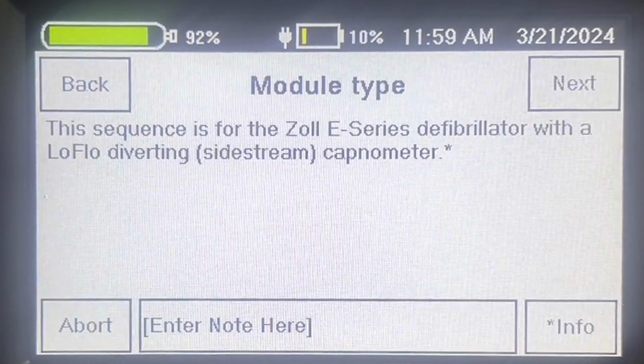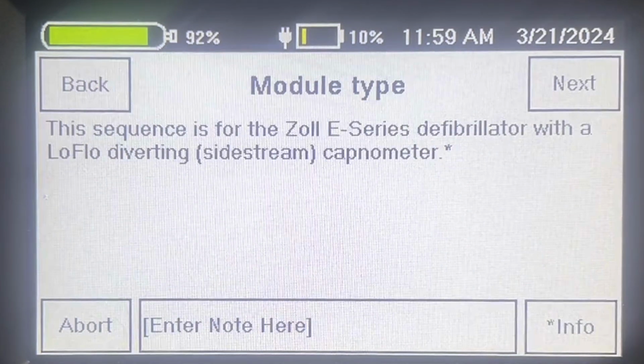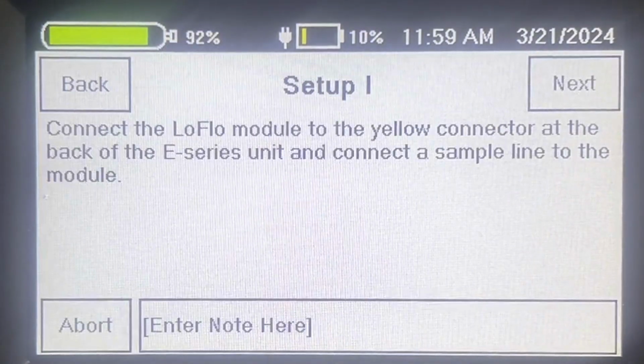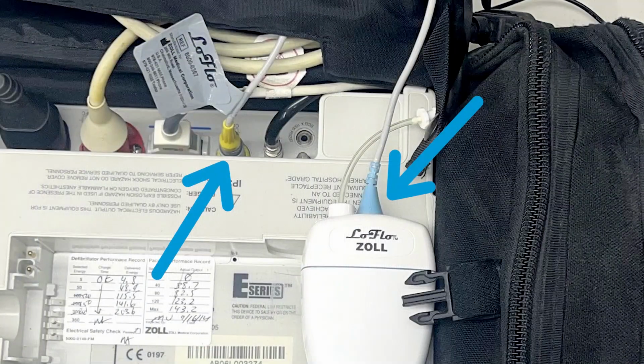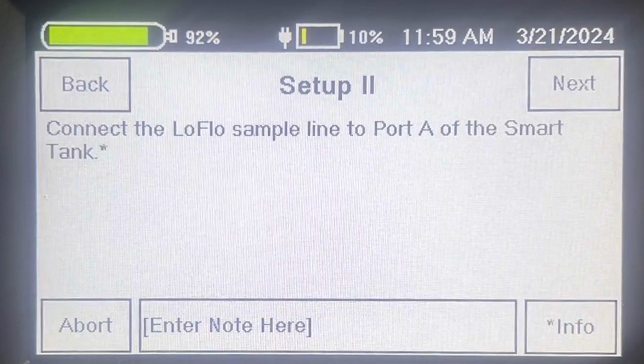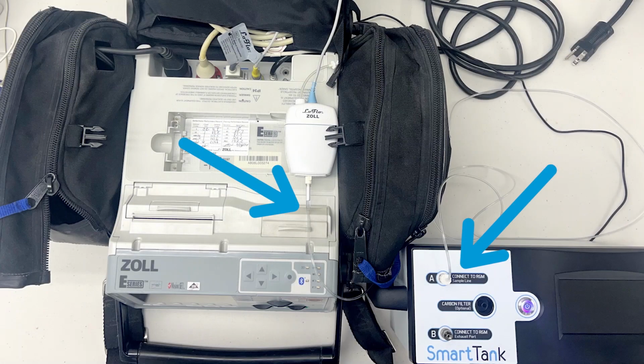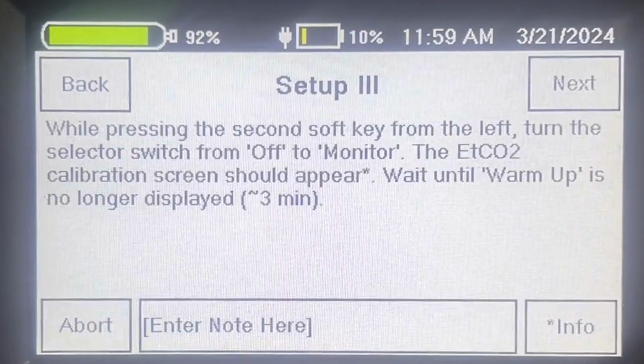Make sure we have the correct module type, or Zoll E-Series defib with the LoFlo. Click Next. Setup 1 is making sure that our LoFlo module is connected to the yellow connector at the back of our defibrillator, which I have done, so I'll click Next. Setup 2 is connecting that sample line from that LoFlo to port A of the Smart Tank, which you will see an image of. So I'll click Next.